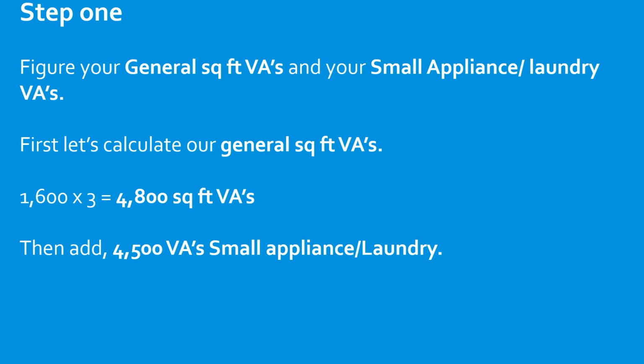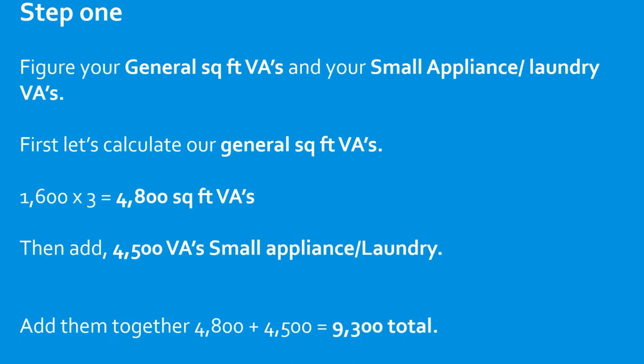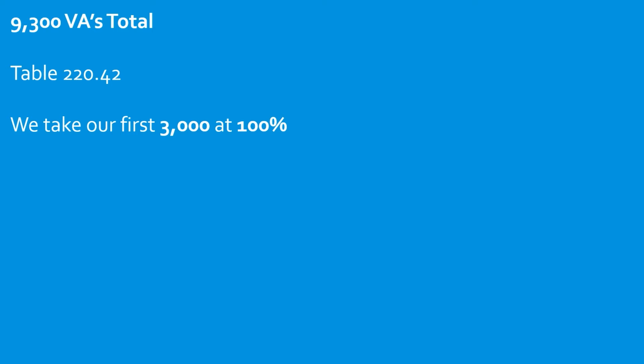If you notice, our question mentioned nothing about small appliance and laundry. They just assume that you know that. Then we add them together. That's going to give us 9,300 total. Okay, so we have 9,300 VAs total, but we need to stop now and go ahead and apply demand factors to this portion of the calculation. So we head to table 220.42. We take our first 3,000 at 100%. In step 1, you take your total minus the 3,000. That's going to give you 6,300 VAs.